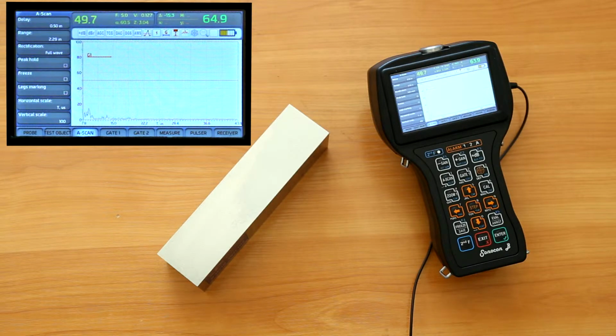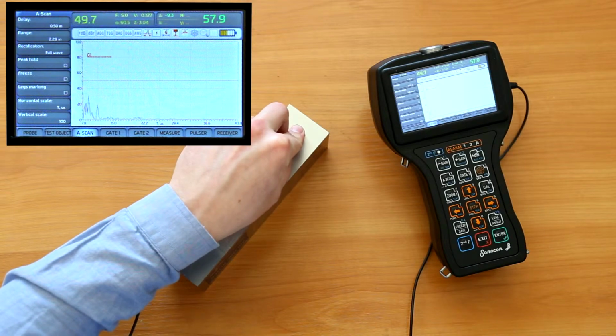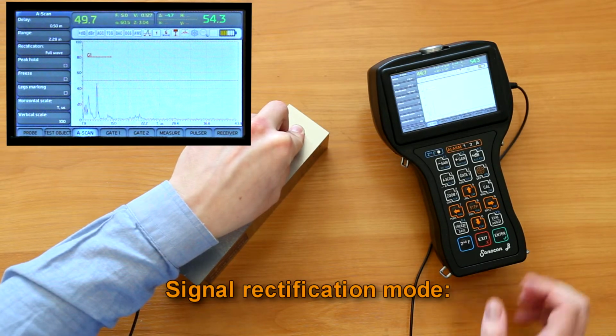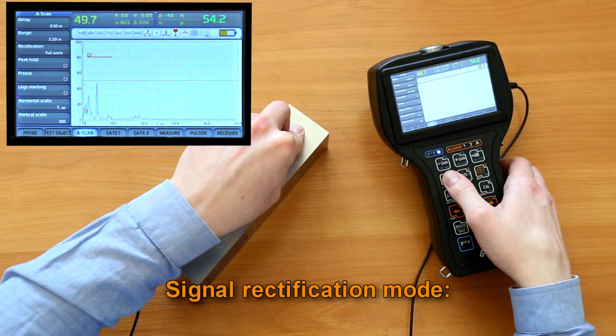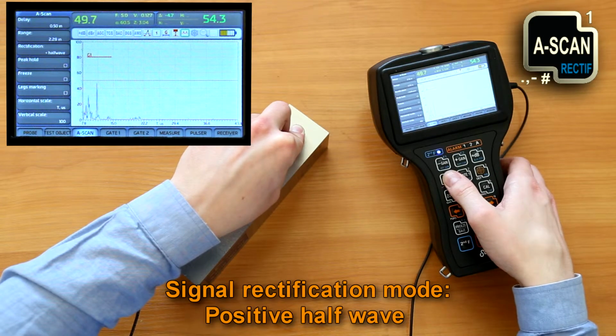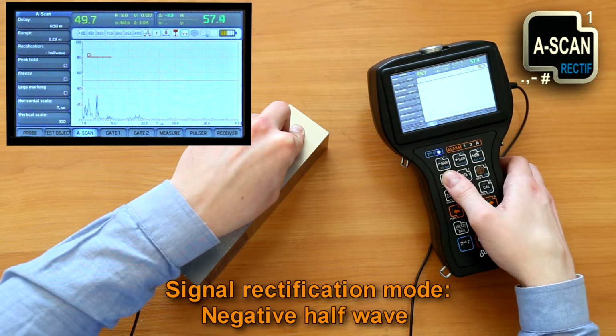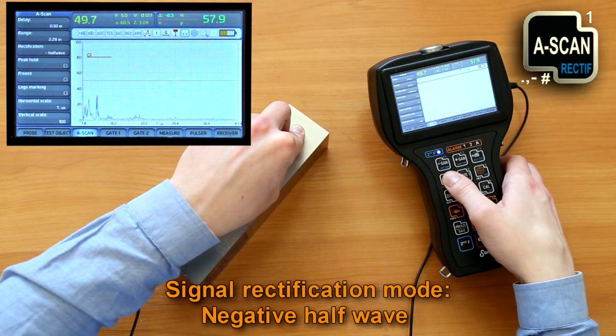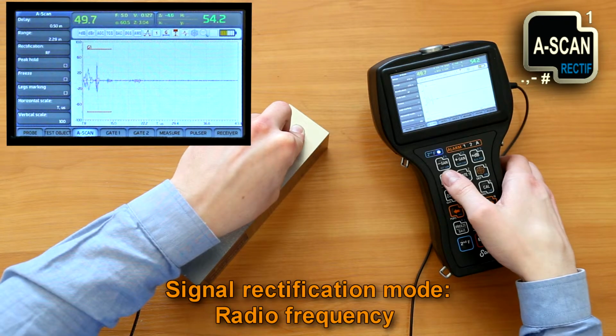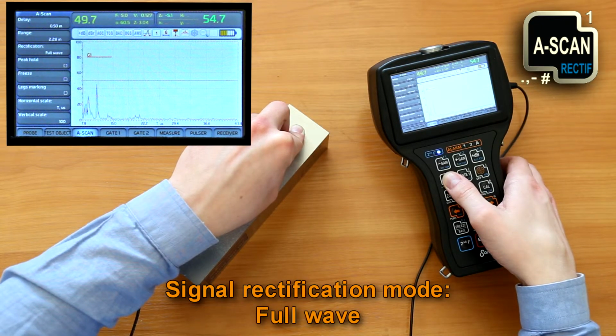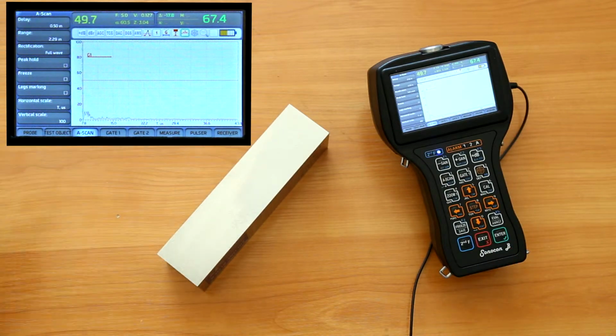Second function plus A scan, and successive presses of the A scan button, will cycle the signal rectification mode: full wave, positive half wave, negative half wave, radio frequency, and go back to full wave. Press second function or exit button to quit this cycle.